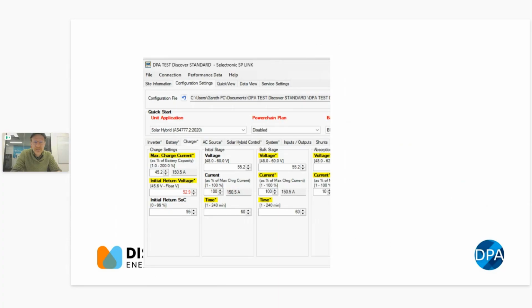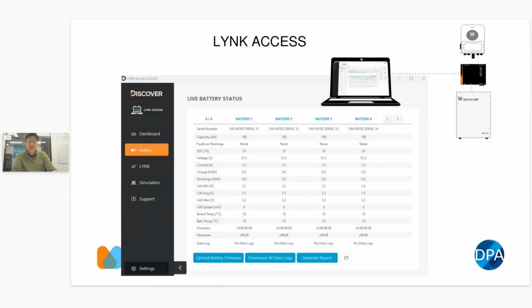Or if you're a glutton for punishment, you can go into Selectronic's long-winded menu and set all the settings by hand. So the LYNK Cloud, well, any questions on that, let me know. We've noticed that the data sheet says 40 amps pass through on the 6 kilowatt and 50 amps on the 8 kilowatt, but we're seeing them trip at 35 and 45 respectively. So the data sheet is out.